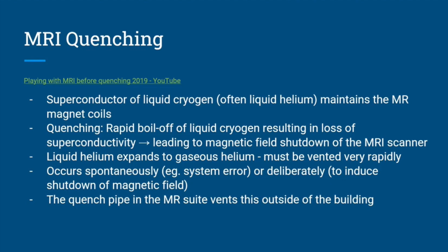And there are safety features within the MR suite which detect inadvertent spontaneous quenching. Because if the quench pipe is blocked, the MRI room becomes a hypoxic environment because it fills up with helium. So in the MR suite, there are oxygen sensors, pressure equalization systems, and ventilation controls to help alert staff and evacuate appropriately. I think each MR unit would have its own emergency quench protocol, and staff should be aware of it. I'm personally not aware of the one at Esch, but I think there should be one, or there is one.